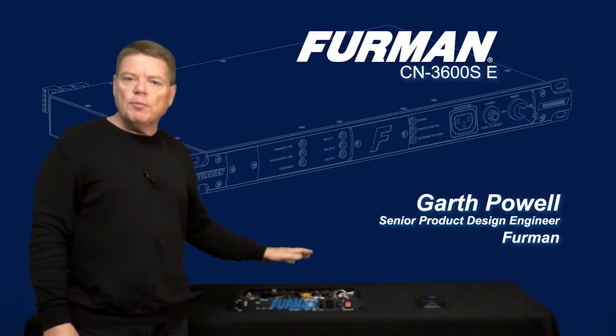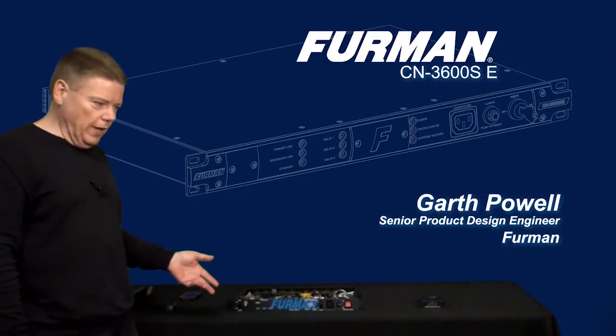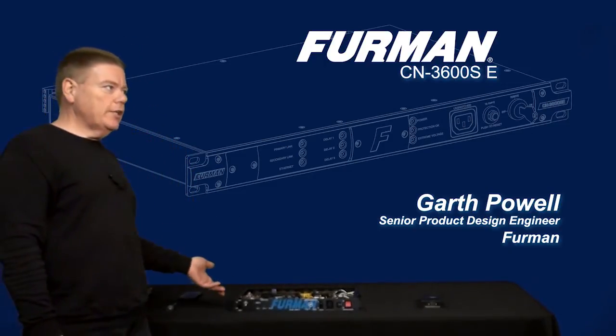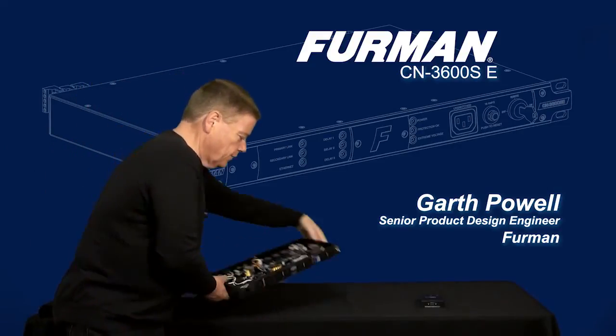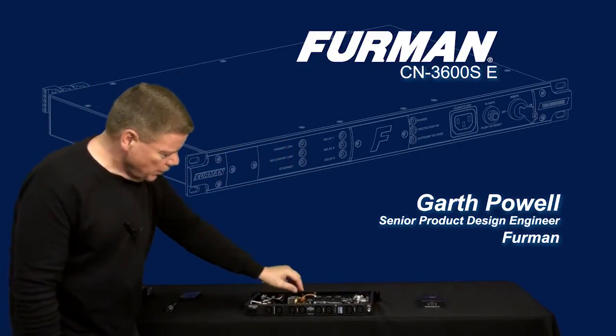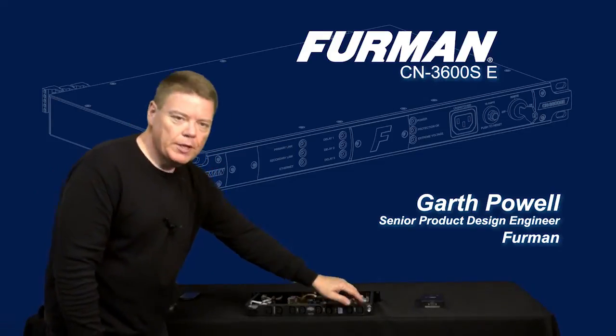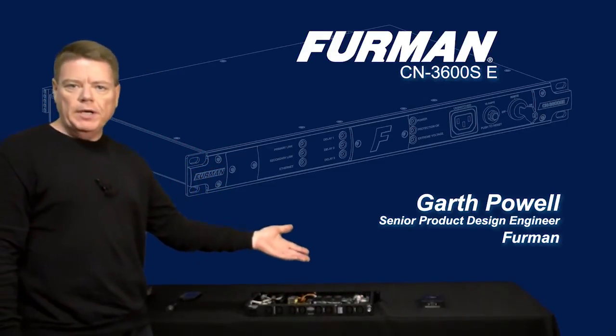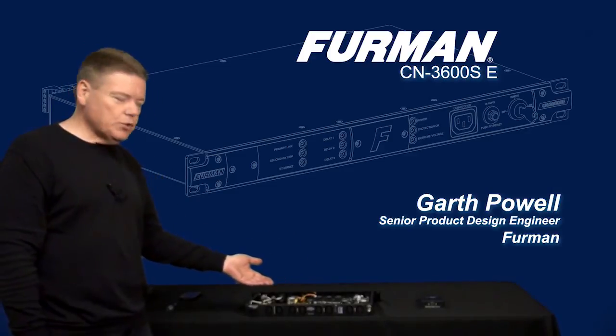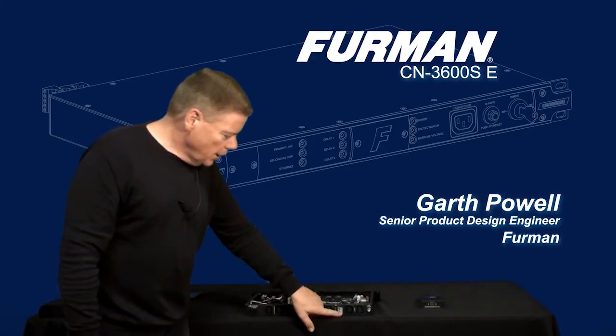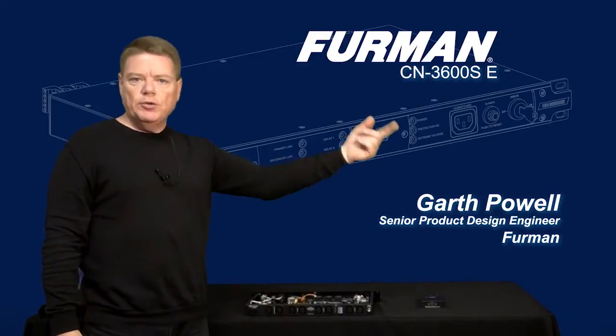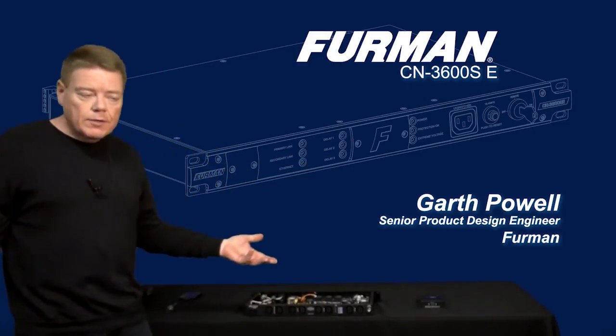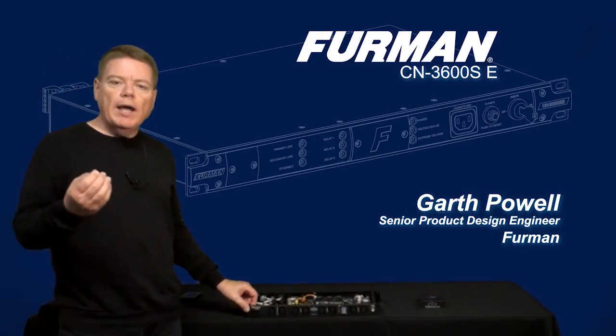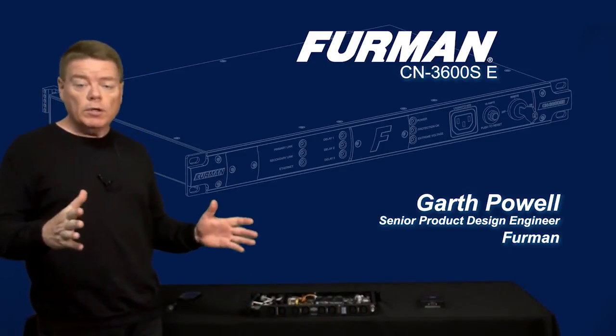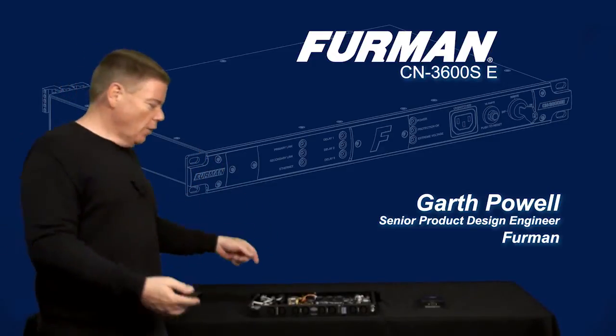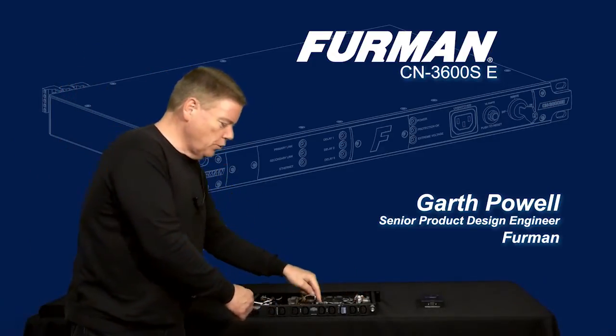Without an outside third-party controller, the problems we had were that, for one thing, we could certainly ensure that all of the sequencing banks, unswitched, delay 1, delay 2, delay 3, we could make sure that we had up to a minute of delay and as little as a quarter of a second between each one. But once the wiring from this unit was daisy chained to another in lengths up to 100 meters, the problem was that when it came time, without the third-party controller, to sequence down, they were all going to sequence down together, 3, 2, 1.